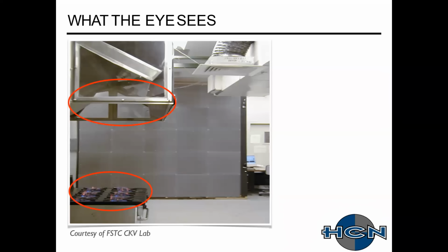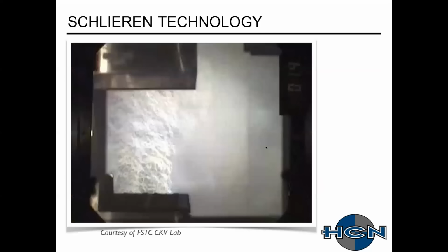Through research project 1376, this was taken from the Food Service Technology Lab in California. They've done a lot of third-party testing on listed hoods and unlisted hoods, and they do a lot of work with ASHRAE. Here you have an oven running pretty much full tilt, and you're not seeing any smoke, so you're assuming the hood's doing its job, capturing that convective load. But using an infrared camera, you see that heat load slightly spilling out right in front of this hood. In reality, this would typically pass a smoke test out in the field, but you're adding a different load to that space. So you would in reality be failing a capture.